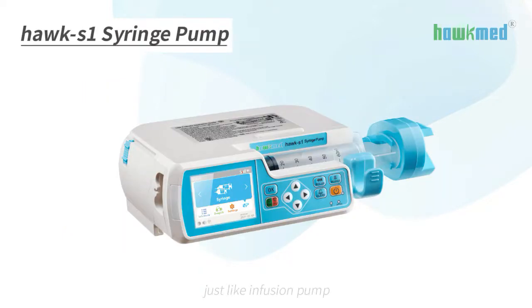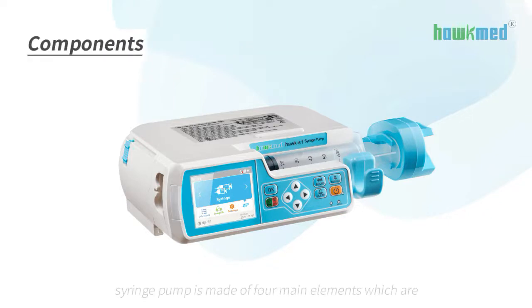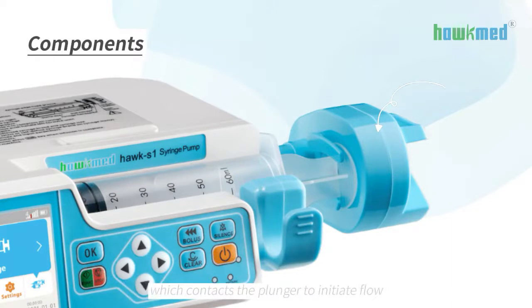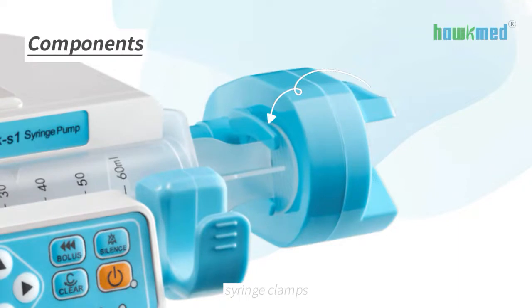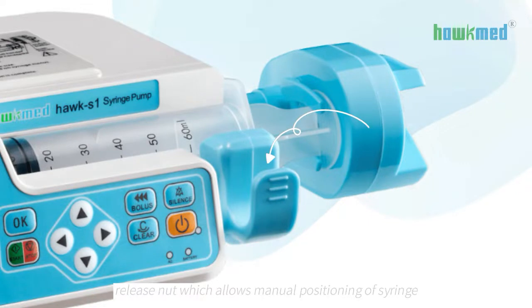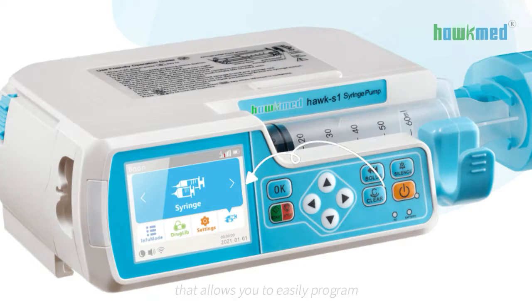Just like infusion pump, syringe pump is a small positive displacement pump used to gradually transfer precise volumes of fluid. Generally, syringe pump is made of four main elements: the pusher block which contacts the plunger to initiate flow, syringe clamps which hold syringes in place during operation, release nut which allows manual positioning of syringe pusher block, and a control panel that allows you to easily program flow rates and volumes.